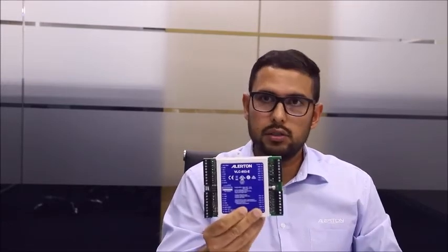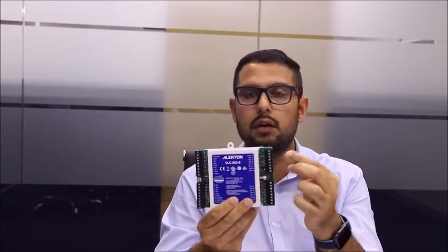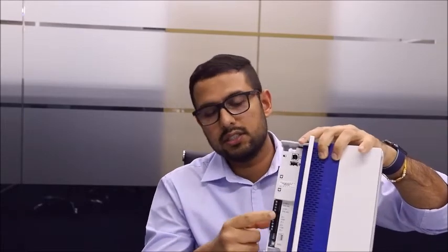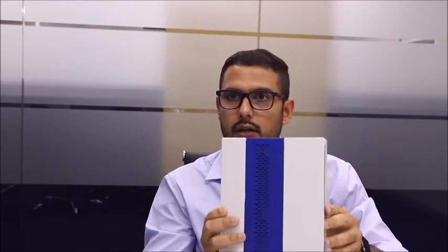So the BMS has some low-level controllers. It's got some temperature sensors going in, some fan start-stop commands going out. And then this controller talks to a global controller, which is fairly big. It's got some IP ports connected here based on your device, if it's IP based, or if it's just low level, it's got some COM ports here. And this is the one which hosts all the graphics and all that stuff, the graphics that I've just shown you. So this big guy has some communication ports that can talk to third-party devices.